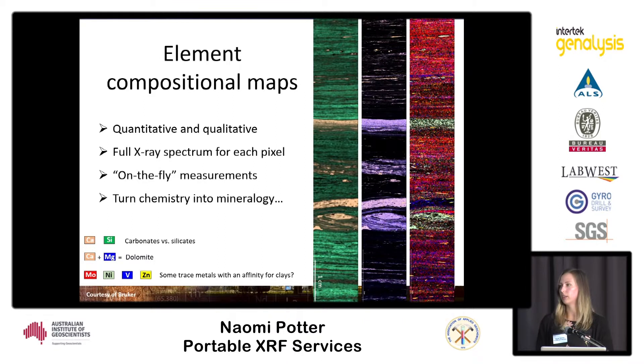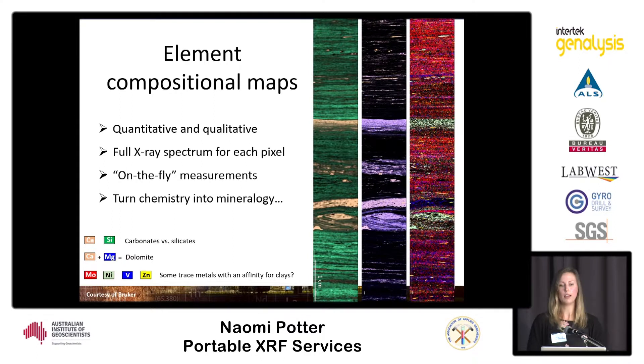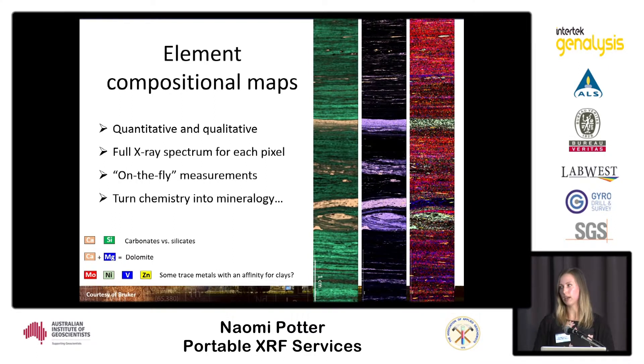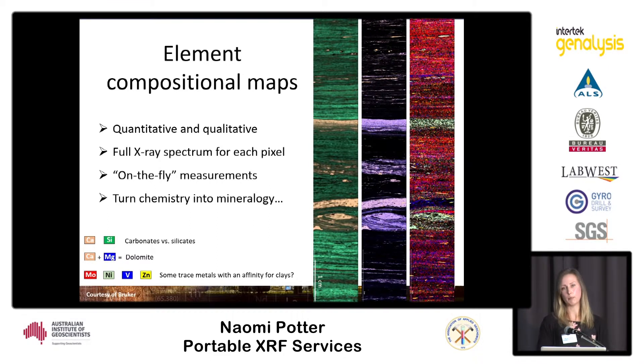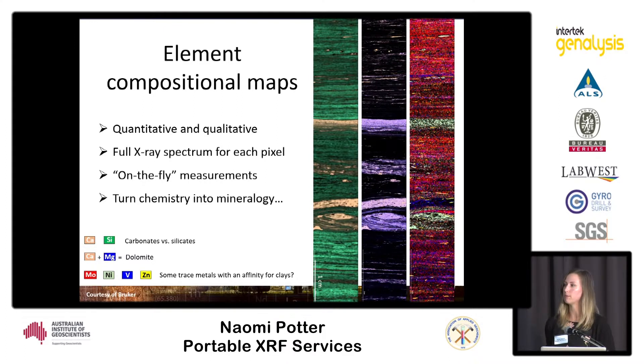When you analyze your sample with the micro XRF, you create an element distribution map. This is done by collecting an x-ray spectrum for every single pixel within your sample, and this can be done on the fly — meaning that as the instrument moves across your sample it collects the spectrum as it goes, which means it can get the data much quicker and takes much less time to complete your analysis.